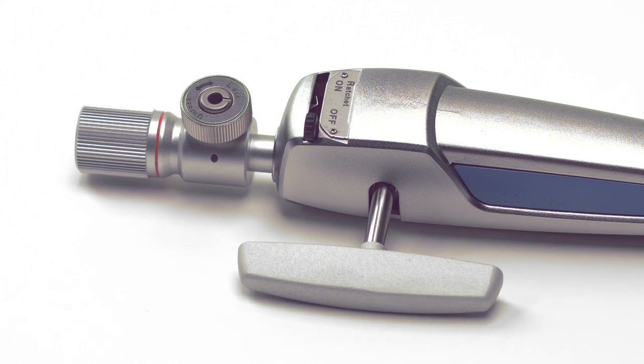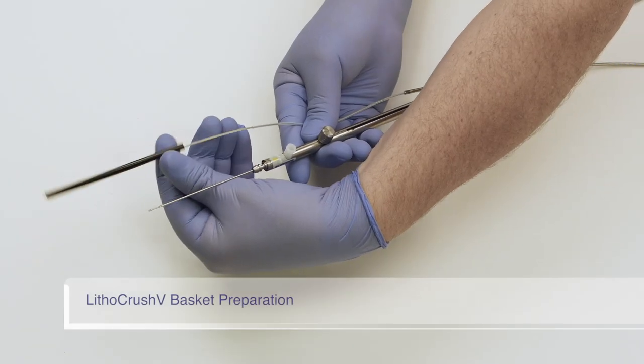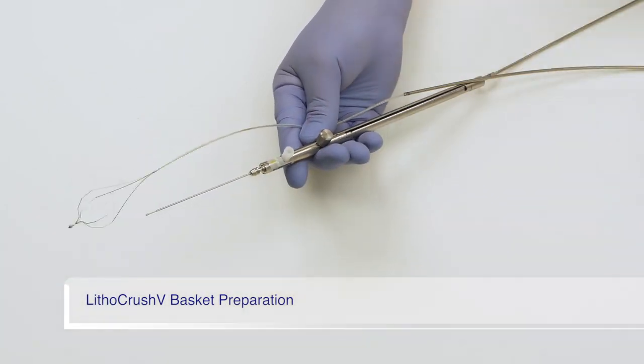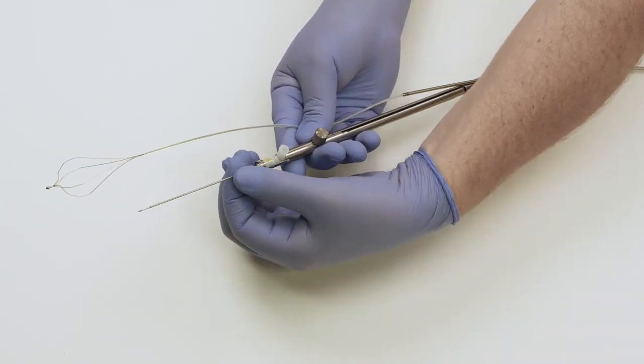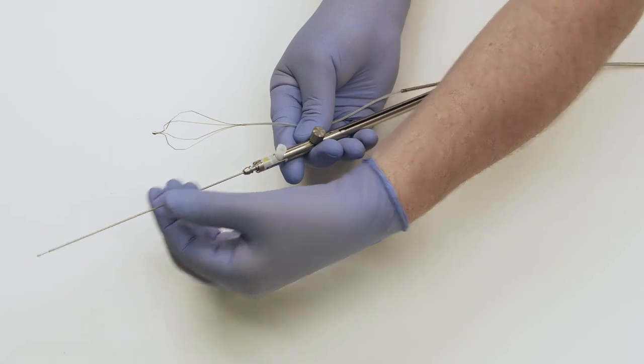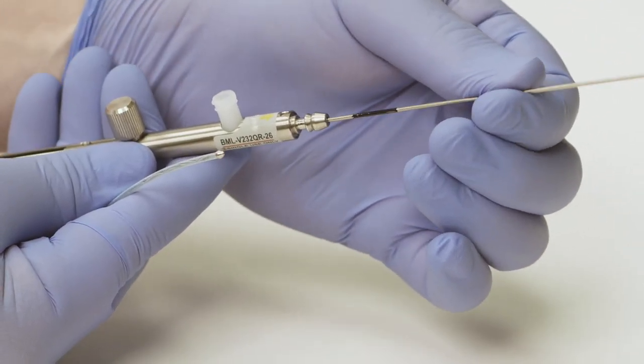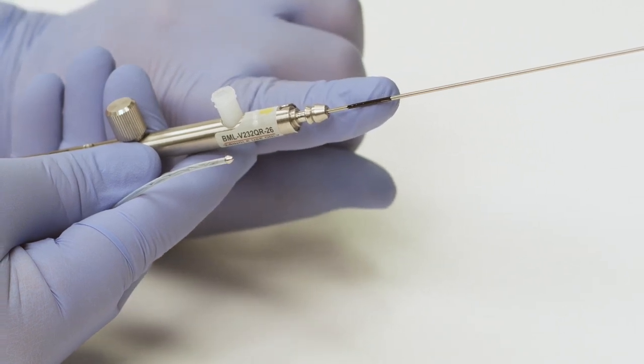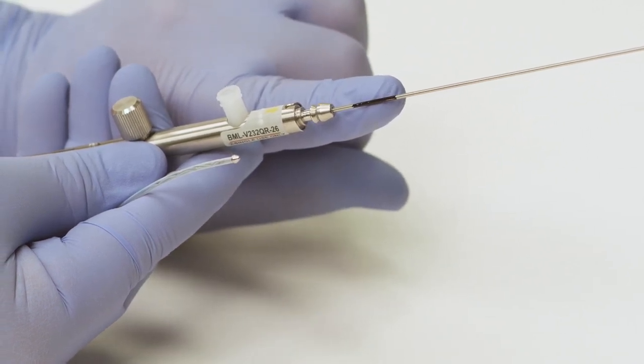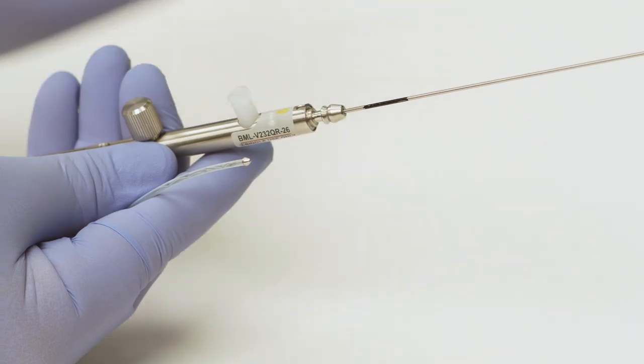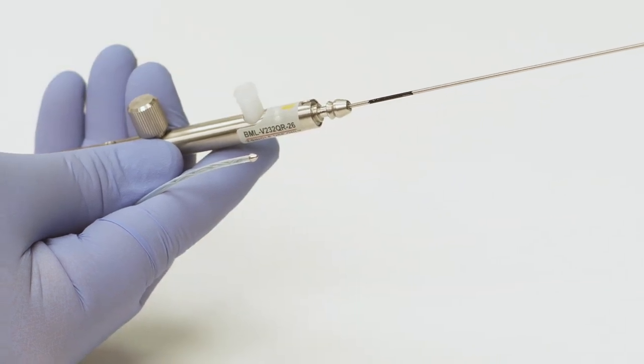The handle is now ready for assembly to the LithoCrush V basket. First, remove the black protective sleeve from the tip of the basket. Second, withdraw the stem at the proximal end until the basket is fully retracted. When the stem is fully withdrawn, a black mark will be visible on the stem. This indicates the basket is ready to be assembled to the handle.